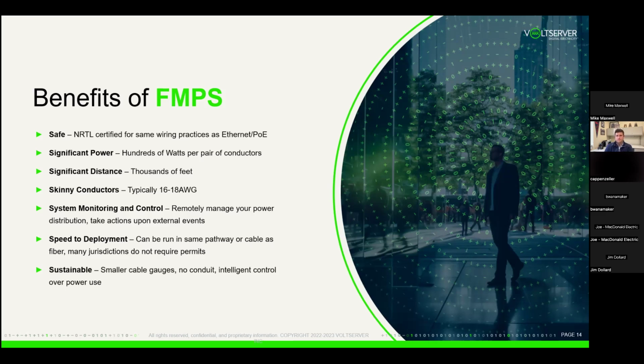And today, they also have a new version that is brand labeled through VoltServer that is a Class 2 hub that has a terminal block on the front that takes up to 4 channels of digital electricity in the fault managed power and provides Class 2 56 volt ports out the front as well. So it can operate like a little power system. The fault managed power system is backed up, feeds the Class 2 hub. The Class 2 hub then can feed 16 channels of Class 2 power out to the loads. So that's one version of utilization equipment that's being done today with an embedded receiver.